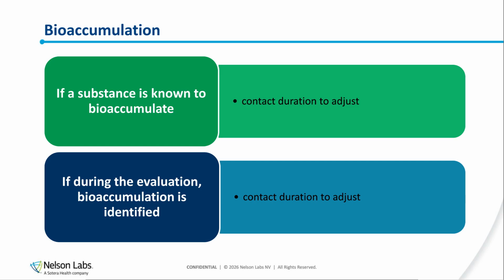The idea is that the repeated contact with the device does not allow for the metabolization of the substance. There is not enough time for that between each exposure. And so the substance keeps building up in your body, which means that the contact duration is not limited or prolonged anymore, but can go up to long term. That is if you know from the get-go that you have a substance that is known to bioaccumulate. But if during the evaluation later on you identify that there is a bioaccumulative substance, then you need to adjust the contact duration even later on. So if you have reached your BER stage and you have now discovered that one of the substances within your device is known to bioaccumulate, then you need to retroactively do the adjustment.